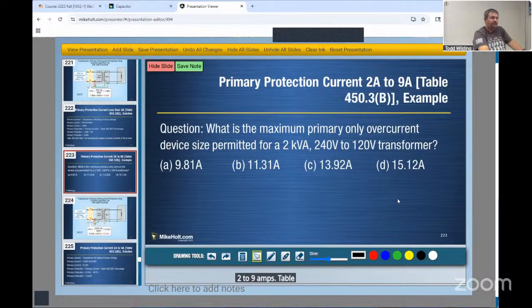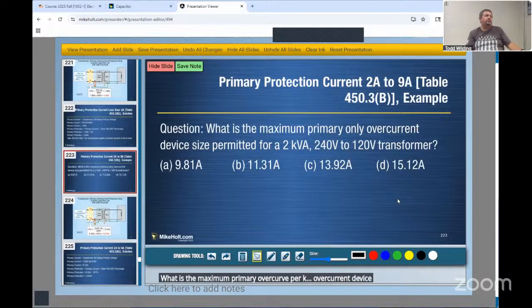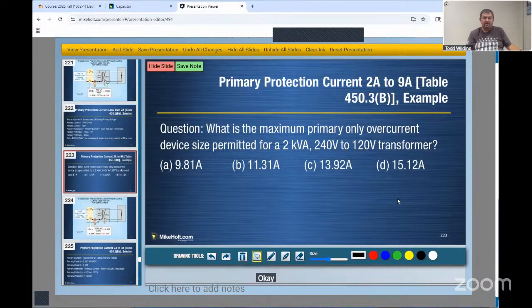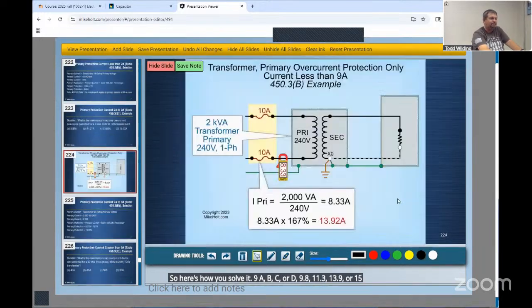Table 450.3(B). What is the maximum primary overcurrent device size permitted for a 2 kVA 240 to 120? Okay. 2 kVA is what? 2000 volt amps, right? Move your decimal, k, 2000. So here's how you solve it. A, B, C, or D: 9.8, 11.3, 13.9, or 15.1.